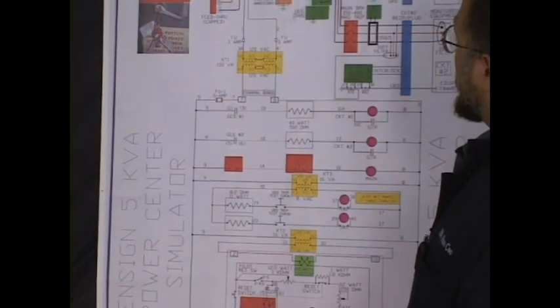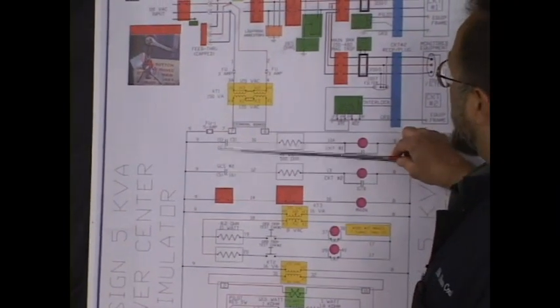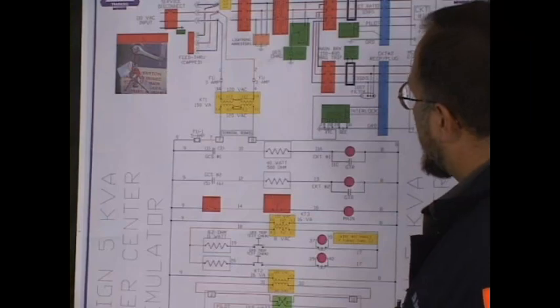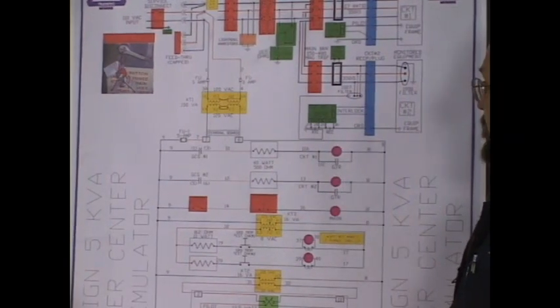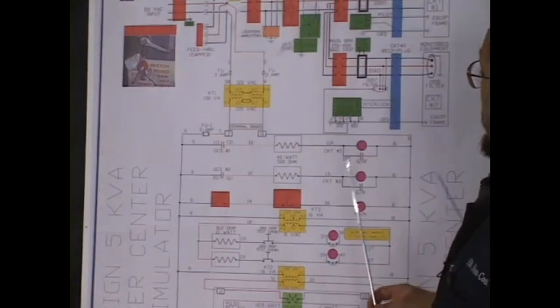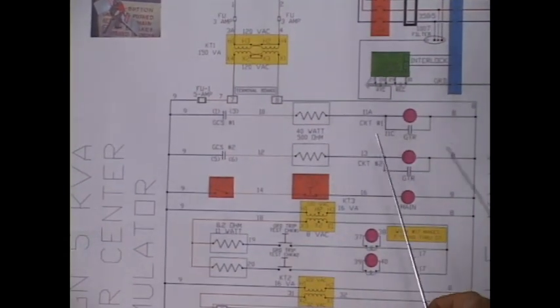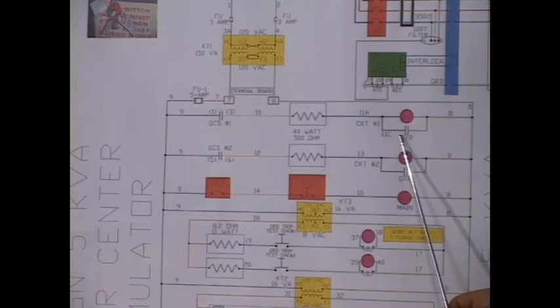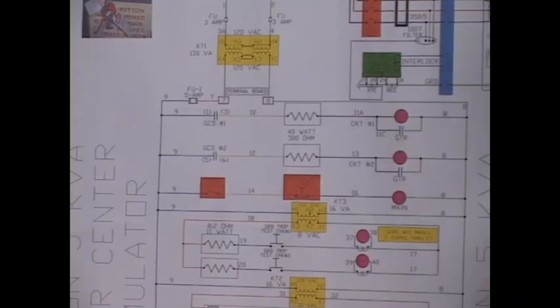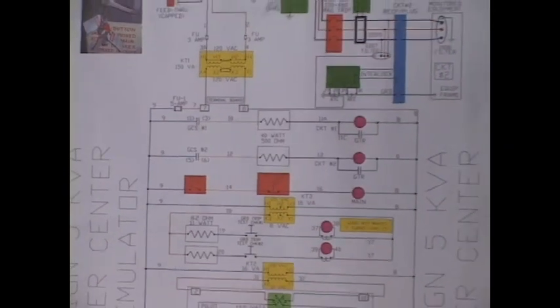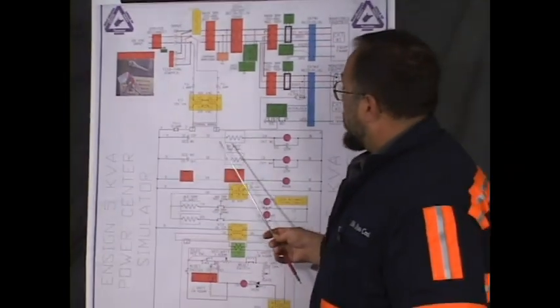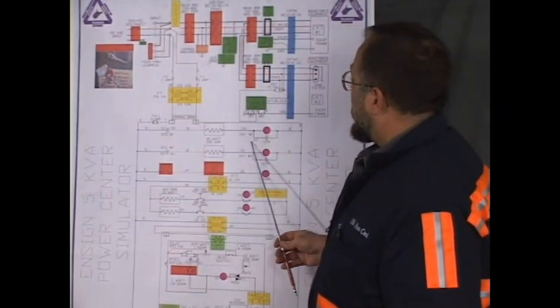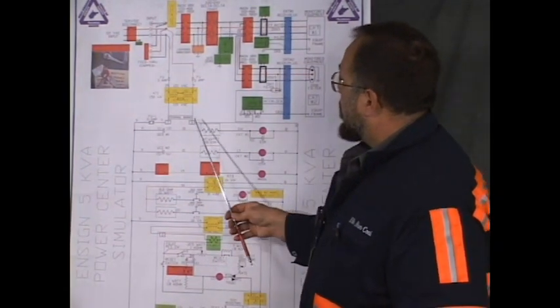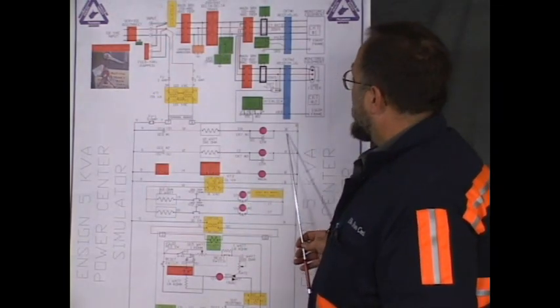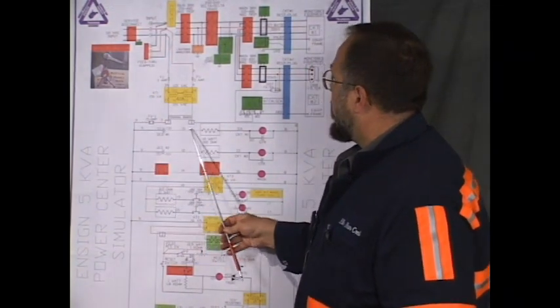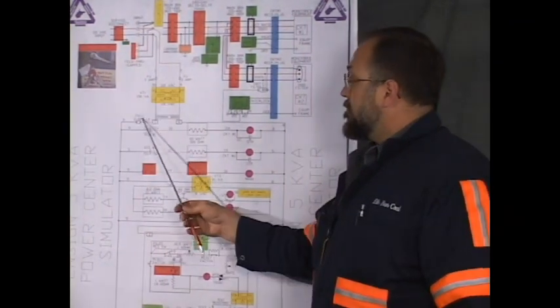Circuit number 1. As you can see, there's the 40 watt 500 ohm resistor referred to in the problem card, in series with UVR for the circuit breaker number 1. Its purpose for being there is to accommodate the GTR tips closing. The contacts for GTR make when you have a ground fault. The ground trip relay tips, when they close, if it were not for this resistor in the circuit, that would make a short circuit. There'd be no load between wire number 8 and wire number 9 that supply this. It'd be a direct short. And the result of that would be a blown fuse.